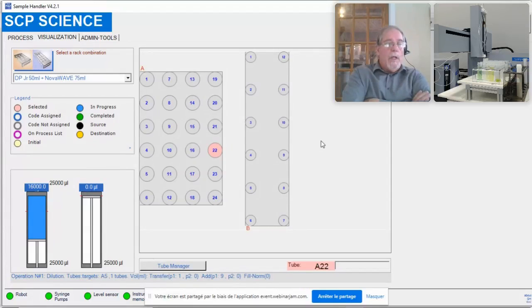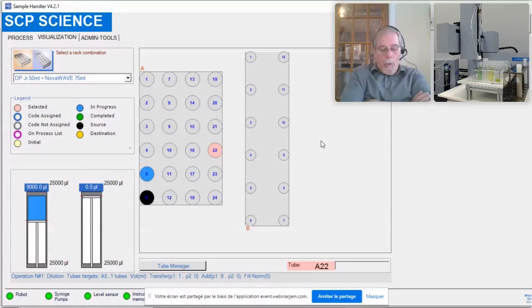When you have a change of reagents, the pump automatically goes through and cleans out the dispensing line. That dispensing line on the sample handler is a 13 mil dispensing line. So we rinse the inside of the tubes and then we rinse the outside of the tubes. The tubes, again, are made out of PFA. They're either a 0.4 millimeter ID or a 1 millimeter ID. So we're not worried about the particle size when you're doing a soil sample for aliquoting.